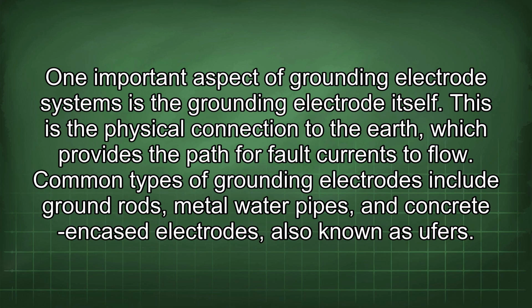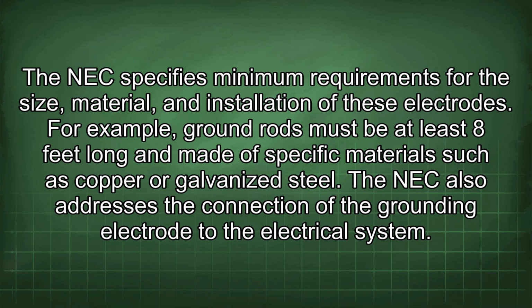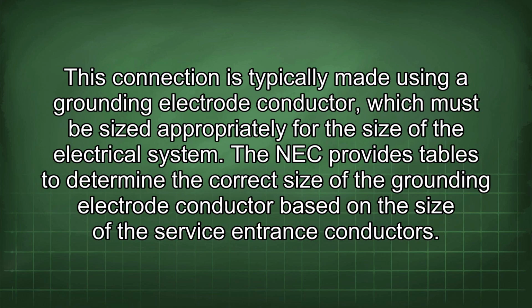Common types of grounding electrodes include ground rods, metal water pipes, and concrete encased electrodes, also known as Ufers. The NEC specifies minimum requirements for the size, material, and installation of these electrodes. For example, ground rods must be at least 8 feet long and made of specific materials such as copper or galvanized steel. The NEC also addresses the connection of the grounding electrode to the electrical system. This connection is typically made using a grounding electrode conductor, which must be sized appropriately for the size of the electrical system. The NEC provides tables to determine the correct size of the grounding electrode conductor based on the size of the service entrance conductors.